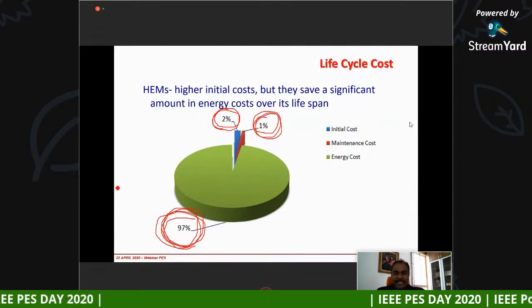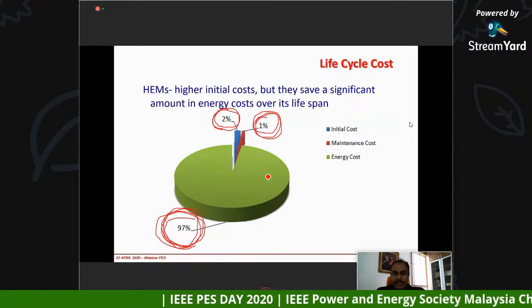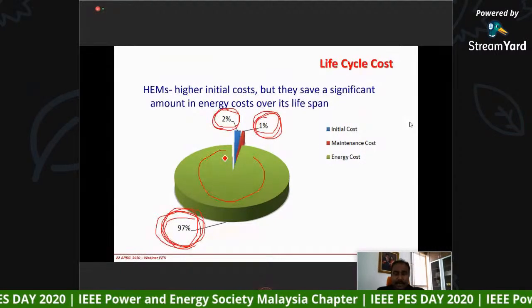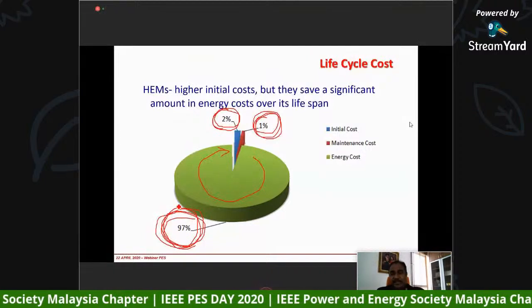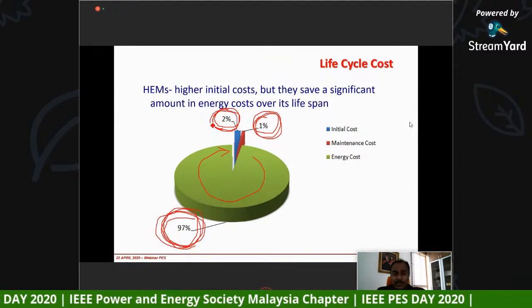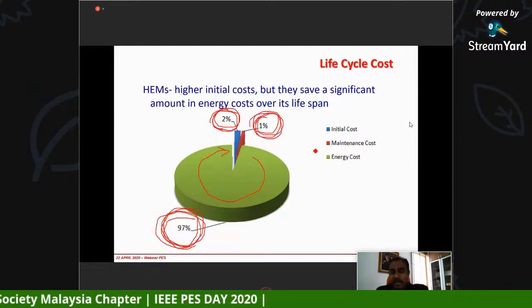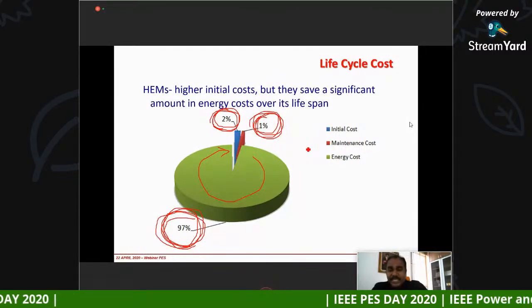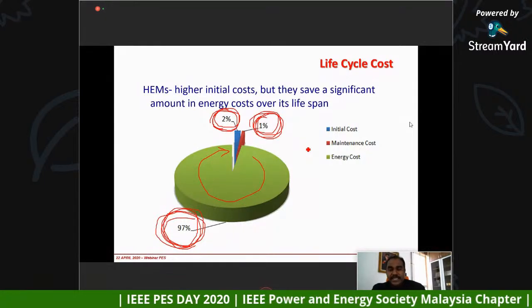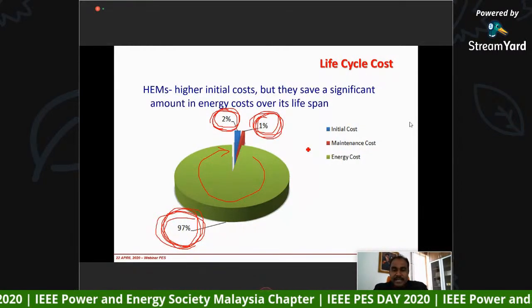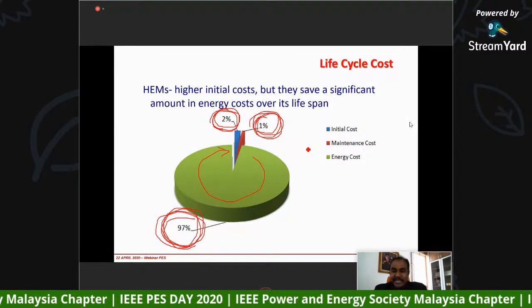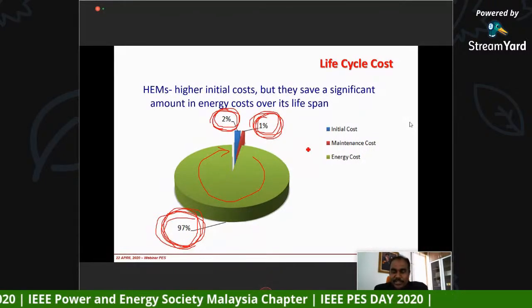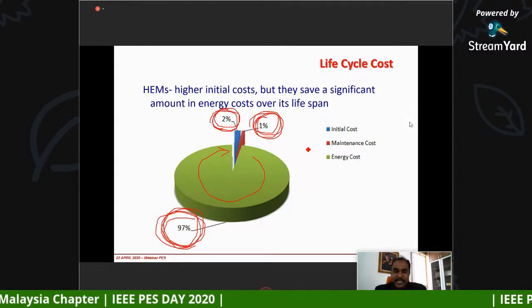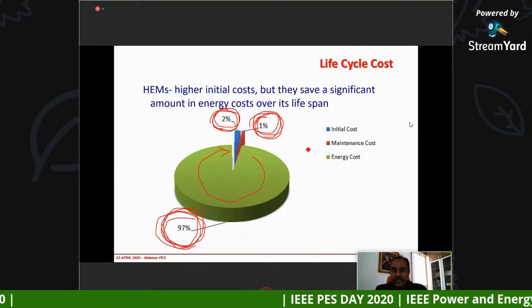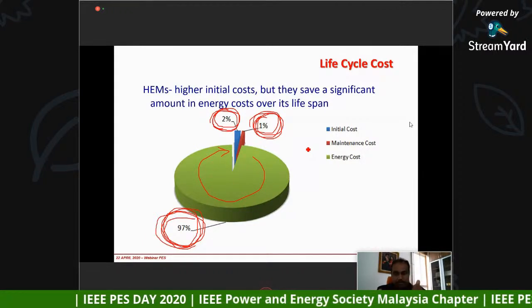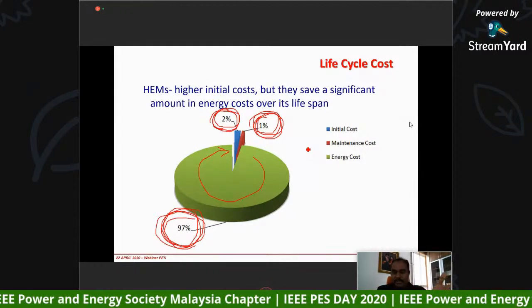then you come out with a pie chart and you will get this kind of pie chart. You will notice that 97% of the cost is actually contributed by the energy cost that you are paying every month. Initial cost is only 2%, and the maintenance cost is probably about 1%. So why should we worry about initial cost? Because you can see savings every month. Most of the time when we calculate, within 1 or 2 years you will be able to get back the 30% or whatever the additional cost that you have to spend for high efficient motors, right? So we have to look into the life cycle cost when we decide whether we want to go for high efficient motors or even the variable speed drive.